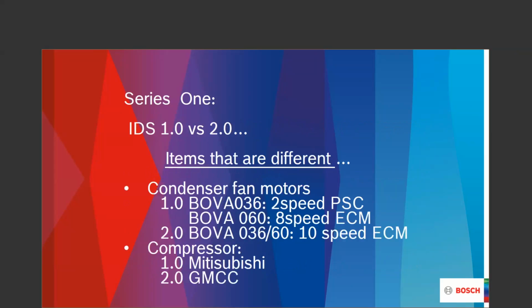Little brother, big brother, if you don't mind, and look at some items that are different. First off, the condenser fan motor. The 1.0 is on the BOVA 36. It's basically a 2-speed fan motor at this time, high and low speed.